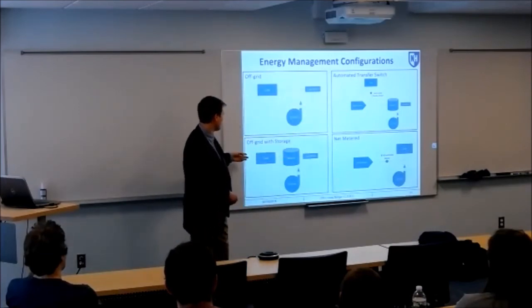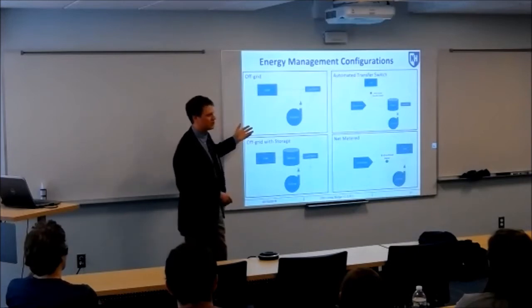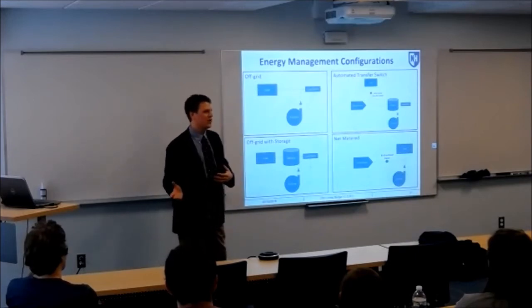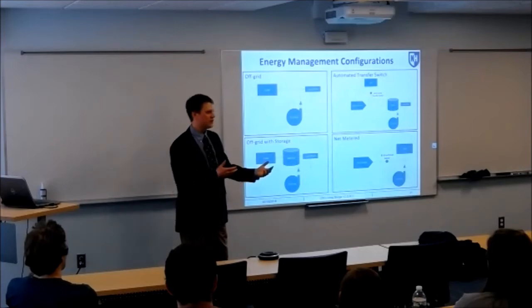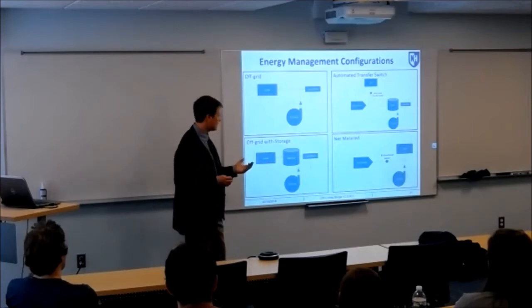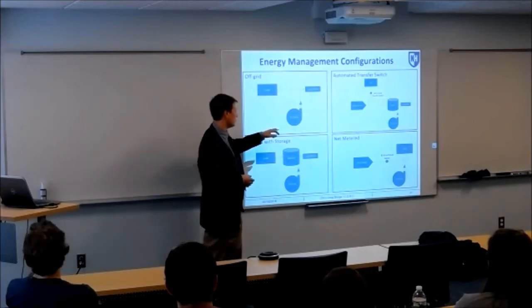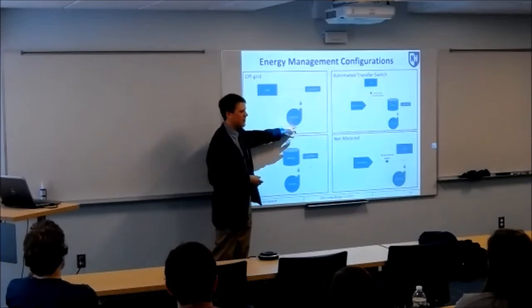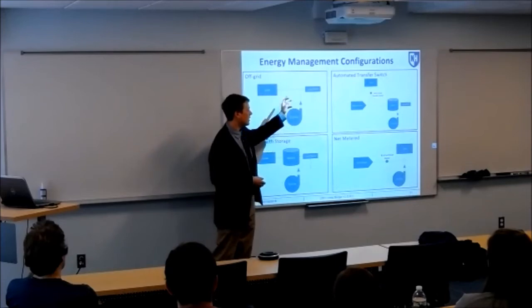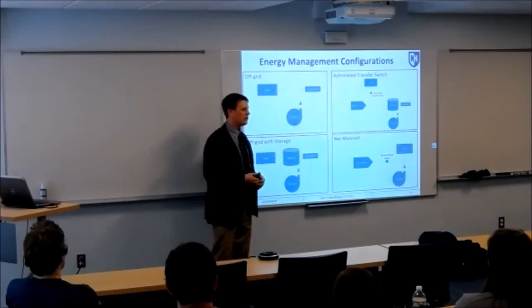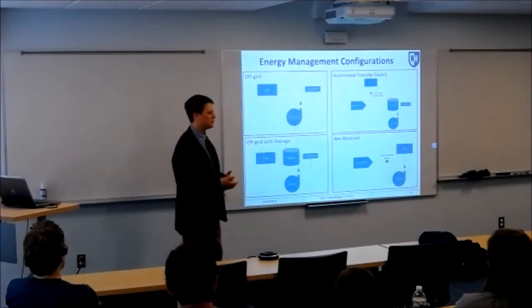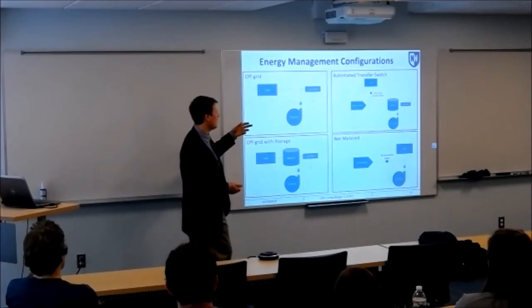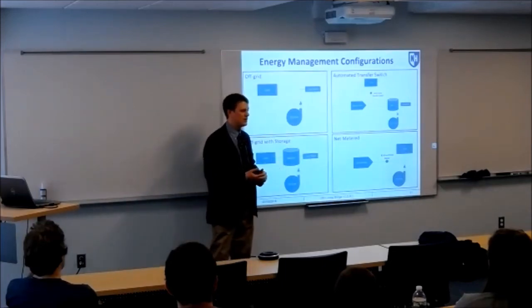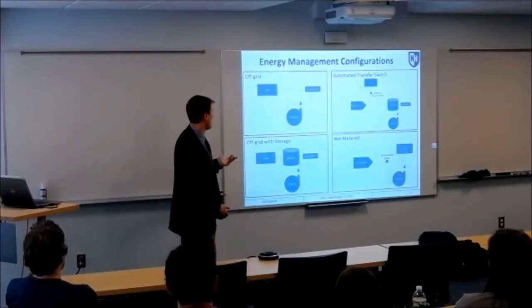A slightly more complicated system has the advantage that you don't have to deal with any permitting with the utility, but it has the disadvantage that you won't utilize a lot of the power the turbine produces. A lot of the time the turbine will be dissipating power through the load bank when it's producing too much, and other times when it isn't producing enough, you'll have to shut down your load.